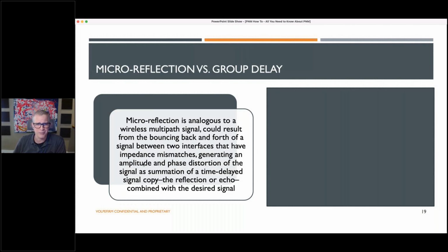So what could possibly happen in a coax network that would cause our coax cables or our connectors to not be 75 ohm? Well, if they're not tightened, if they're loose, we have a non-75 ohm device. If we have a coax connector that has a dent in it, it's no longer 75 ohm. If we get water in our coax cables, they're no longer 75 ohm. If we get corrosion in our coax plant, it's no longer 75 ohm. Any of these things, and there's much more that can happen, will cause our coax plant to not be 75 ohm. All of these cause impedance mismatches, and all of these cause microreflections. These all show up in PNM as microreflections and its badness.